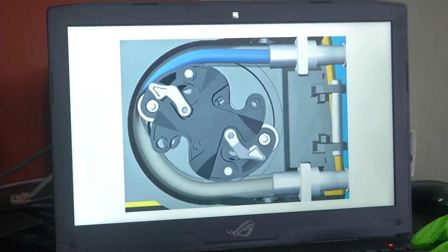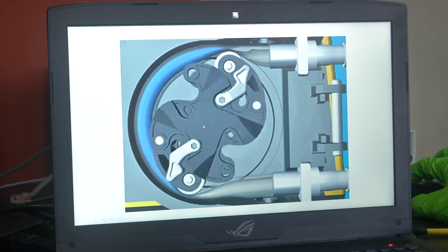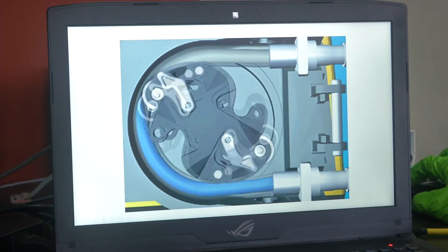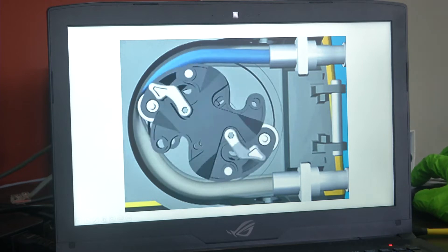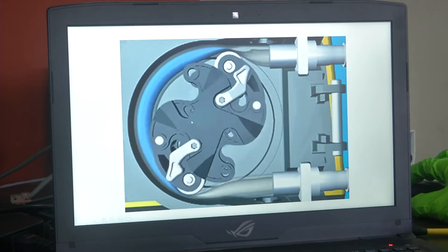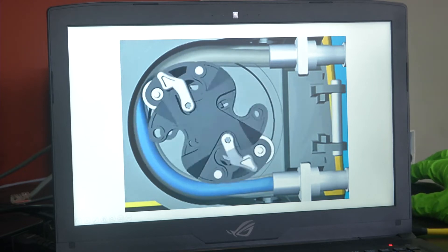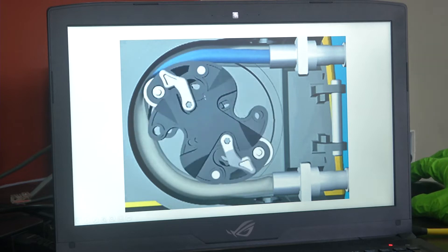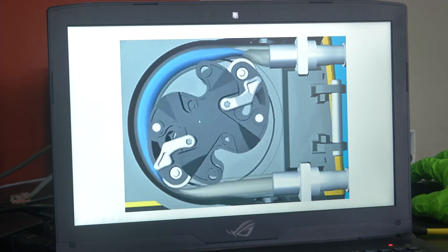I will now show you how a peristaltic pump works using a GIF image. You can see the fluid will come through the inlet port. There is a rotating roller assembly, and within that rotating roller there are also smaller rollers. The peristaltic pump casing holds a flexible tube. When the roller rotates, it comes and pushes the fluid within the tube between the wall and the roller, pushing it to the other end. This is how pumping works in a peristaltic pump — it is a positive displacement pump, meaning the fluid moves only in one direction.